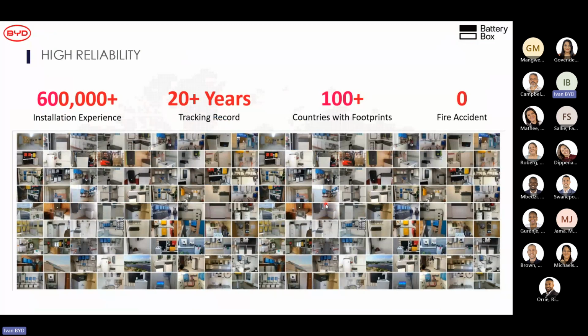I think I'd take this moment now just to explain a situation that happened once, where there was a 200 volt solar array, 5 kilowatts, and BYD batteries, and the solar power converter failed closed, so that 200 volt, 5 kilowatt solar array was directly connected to the DC bus, and the BYD batteries were connected to it. And they're 50 volt batteries, and three of the batteries managed to disconnect, and the fourth arced across. So the solar array was directly connected to the battery. So it's a 200 volt solar array connected to a 50 volt battery. What happened was all that energy that was in the battery and in the solar array got dumped into the battery.